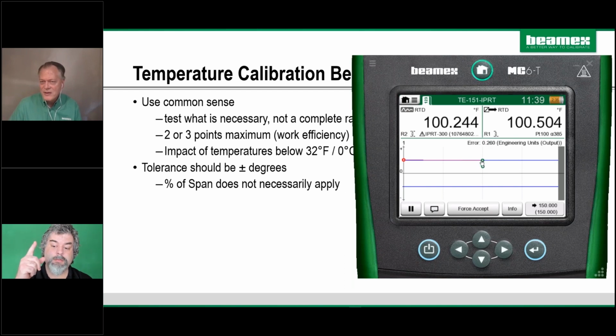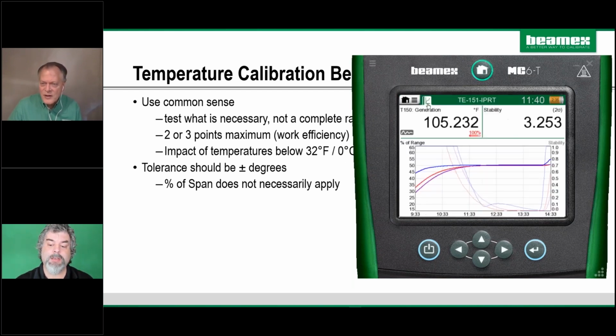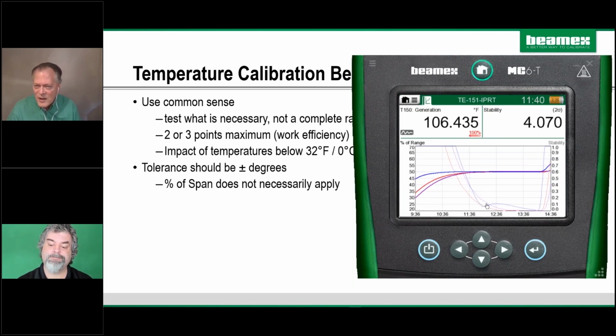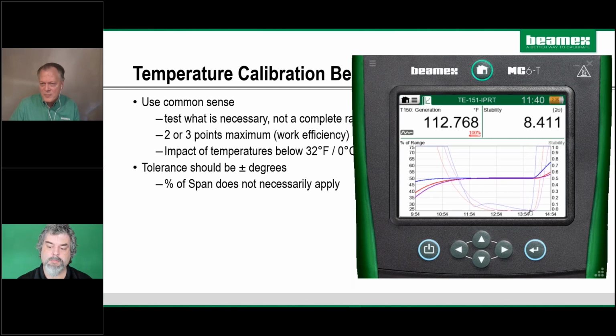So it actually passed at the midpoint here. It was under the 0.5 threshold. It was just barely above there. But let's look over here again. So look at the stability. It got pretty close here. So it was at about the 12-minute mark, but the dry block did wait an extra 2 minutes or so because the stability was kind of still moving. And look, it's recording when the stability's practically zero. And then now we're going to 150. We're going to see the same graph, the same trend that we saw going from 50 to 100.